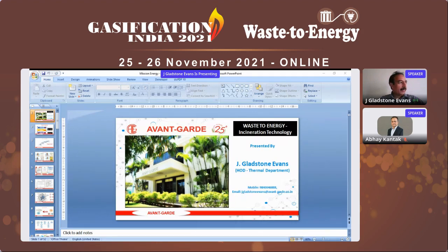And in this, the waste to energy pit is one of the important areas. It is one of the critical areas in the waste to energy plant. First, it reduces the surface moisture, because since you are dumping waste into the pit, it has a lot of moisture in it, especially during monsoon seasons, when the acquired moisture will be more. So by storing it for around 5 to 10 days, the moisture will be collected in the pit. That is one function, so that when the moisture is collected, the calorific value of the MSW becomes high.